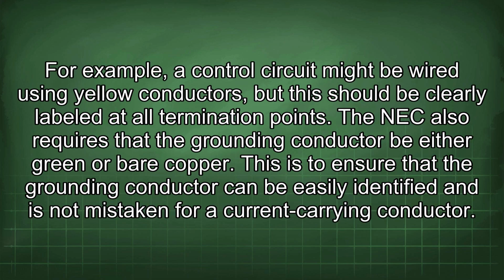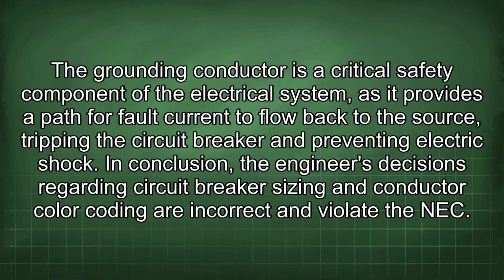For example, a control circuit might be wired using yellow conductors, but they should be clearly labeled at all termination points. The NEC also requires that the grounding conductor be either green or bare copper. This is to ensure that the grounding conductor can be easily identified and is not mistaken for a current carrying conductor. The grounding conductor is a critical safety component of the electrical system, as it provides a path for fault current to flow back to the source, tripping the circuit breaker and preventing electric shock.